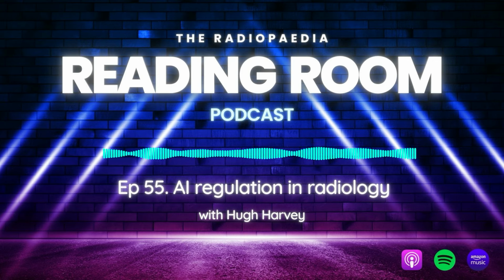Class 2 is much more common. It provides information used to take decisions with a diagnosis or therapy, or it's just monitoring a physiological process. However, if the condition is severe or can lead to a deterioration in health or possibly something like surgical intervention, it could be class 2B. Or similarly, if it's a very vital physiological process, it could be class 2B. And for the high-risk devices, that's when the decision impact of the AI system could cause death or irreversible deterioration. Obviously that's much higher risk, and that's class 3.